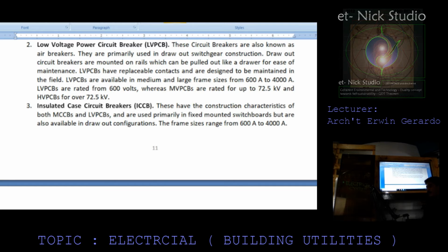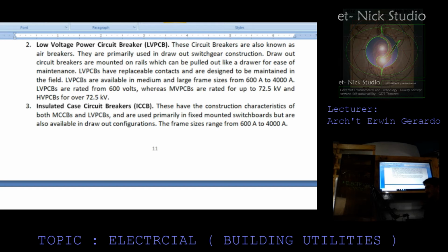Second, low voltage power circuit breaker. These circuit breakers are also known as air breakers. They are primarily used in draw-out switchgear construction. Draw-out circuit breakers are mounted on rails, which are pulled out like a drawer for ease of maintenance. LVPCBs have replaceable contacts that are designed to be maintained in the field. LVPCBs are available in medium and large frame sizes from 600 ampere to 4000 ampere. LVPCBs are rated up to 600 volts, whereas MV PCBs are rated up to 72.5 kV and HV PCBs for over 72.5 kV.